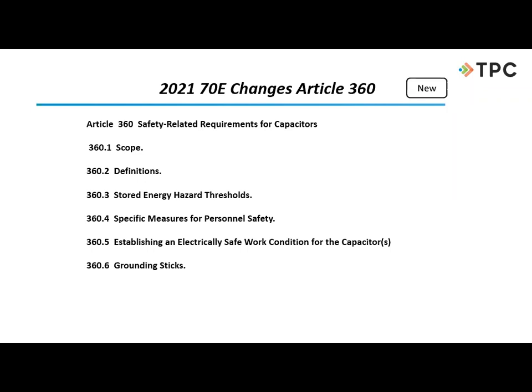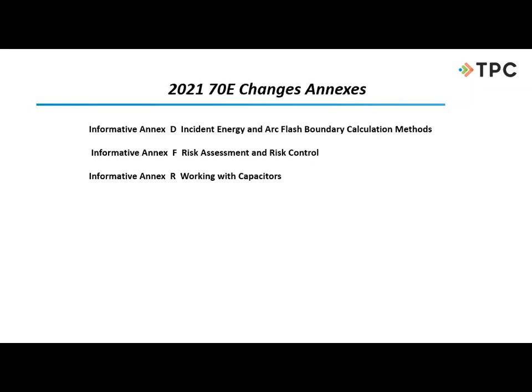360.4 covers some specific measures, which are different than Article 130. Remember, this is a supplemental or modification chapter, and every article in Chapter 3 can change what we learned in Article 130. There's a different way to establish an electrically safe work condition for capacitors, and it talks about how we can ground those out, either a hard grounding or a soft grounding. So it's a brand new article, and I think the technical committee did a great job on that.